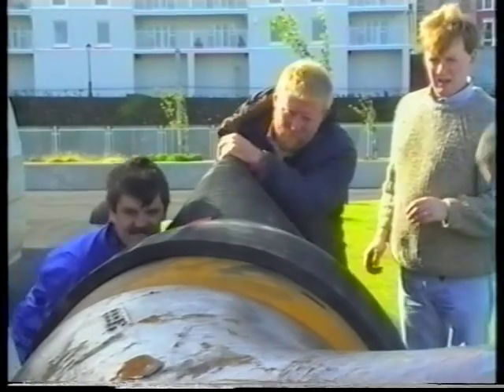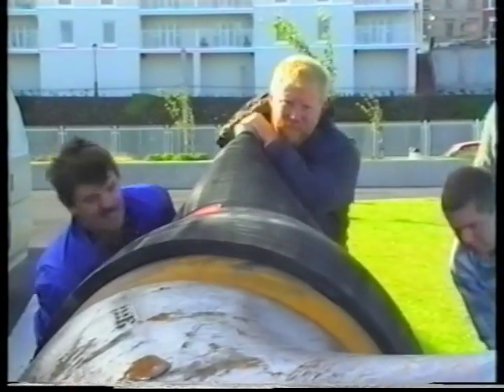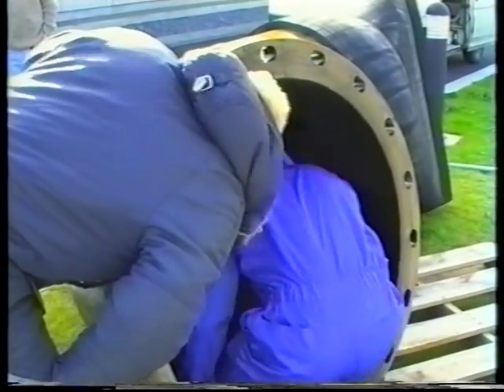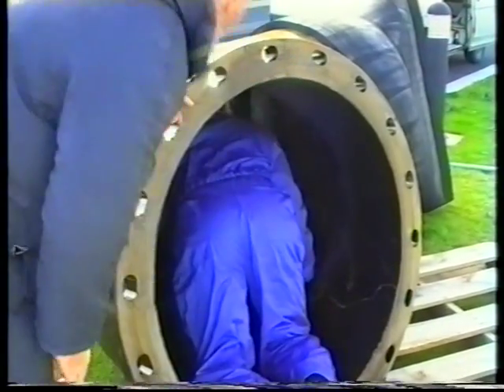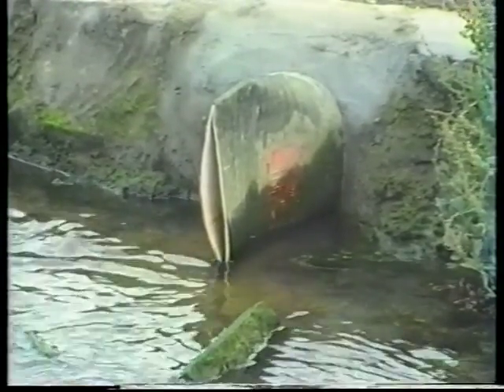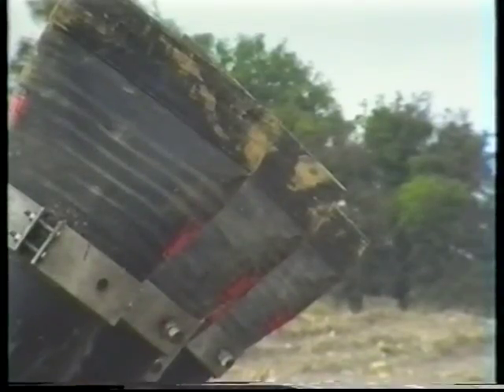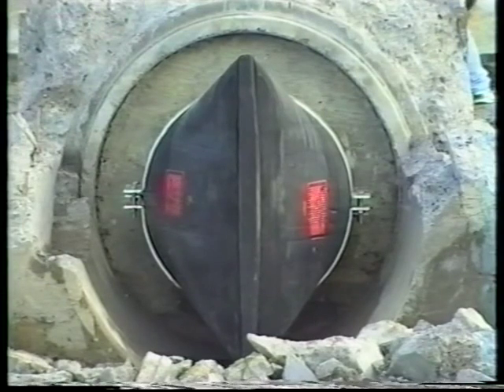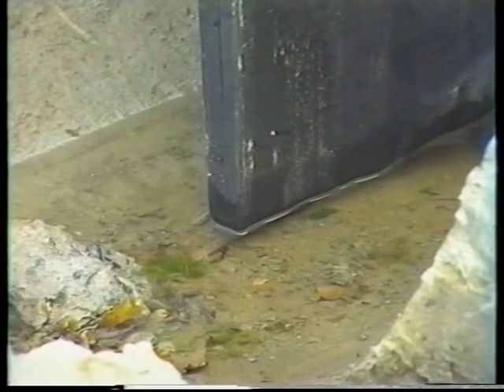Once enough straight edge pipe is exposed, the valve is easily pushed home. A check should be made that it is correctly in place. Improperly seated, the lips of the valve will open and become ineffective. The Tideflex check valve can be installed on any plane in any direction. But on a horizontal pipe, the bill must be mounted vertically with at least 100mm clearance underneath.